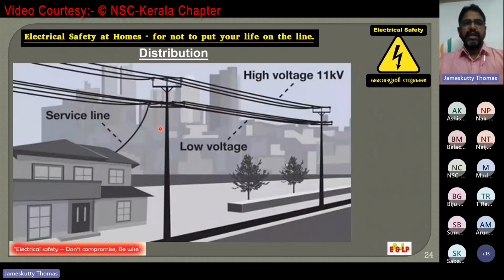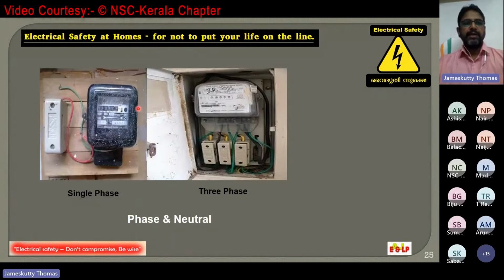Here is the distribution line shown to get you a clear picture. Here is the 11 kV line, then the LT line, which is the service line. Using this service line, we are getting the supply from the KSEB line. Here, single phase and three phase meters are shown. If your connection is single phase, there will be 2 wires, phase and neutral, and if it is 3 phase, there will be 4 wires, 3 phases and neutral.